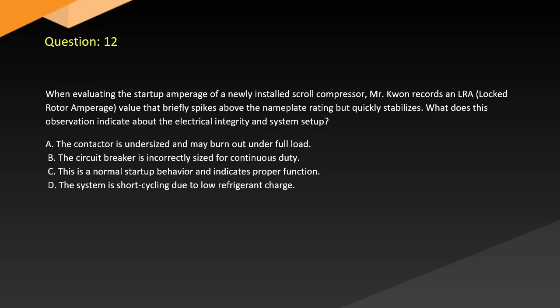Question 12. When evaluating the startup amperage of a newly installed scroll compressor, the technician records an amperage value that briefly spikes above the nameplate rating but quickly stabilizes. What does this observation indicate about the electrical integrity and system setup? A. The contactor is undersized and may burn out under full load. B. The circuit breaker is incorrectly sized for continuous duty. C. This is a normal startup behavior and indicates proper function. D. The system is short cycling due to low refrigerant charge.